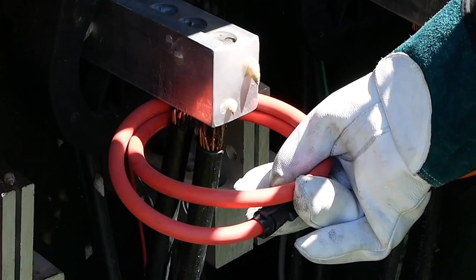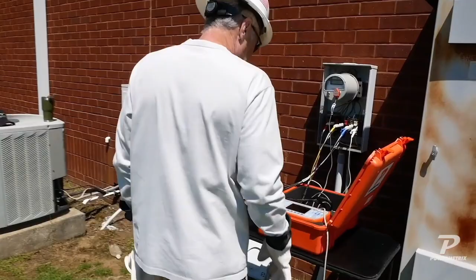So you want to hold it and center it, because remember, on one of these flex CTs, the center is the best spot that you can be in. So sometimes when you've got two guys here, you get a guy to hold it dead center, and we're going to retest it again on A phase and see if we can't get a good test.